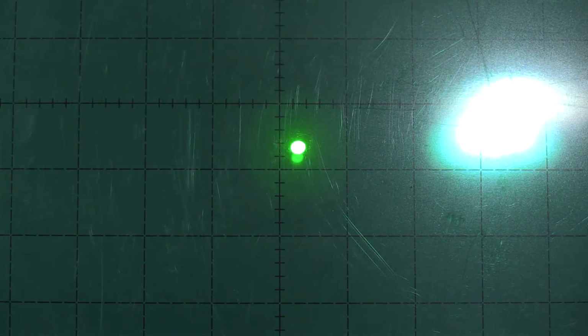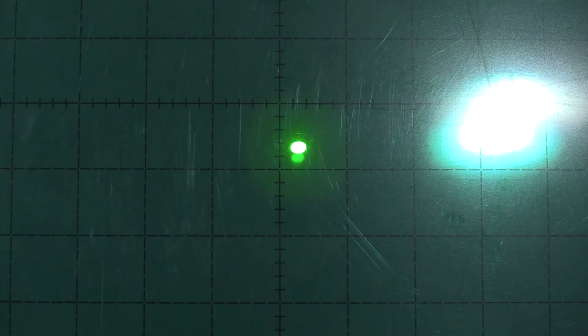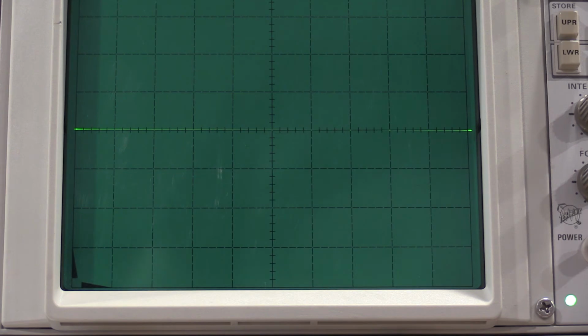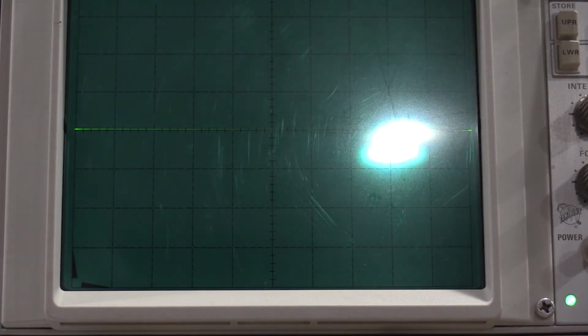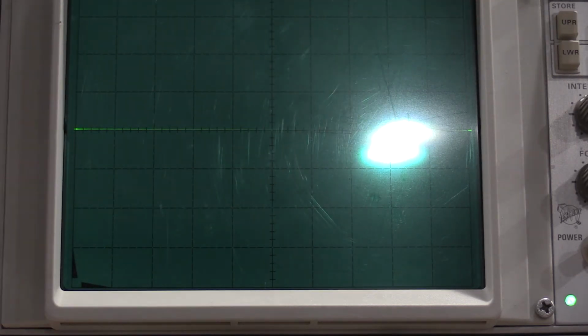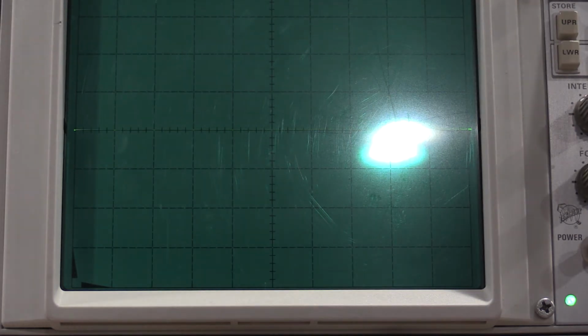Okay, so now we're into astigmatism and trace rotation. So focus control counterclockwise, intensity completely clockwise. Do this fast because you have a very high intensity spot and you're just looking for a round spot, because it can go oval. Just looking for round. Our rotation's off a bit, so it's 0.5 volts on the horizontal and then just 10 divisions of display. But we need to adjust the trace rotation pot. You just adjust the trace rotation pot for a flat display.